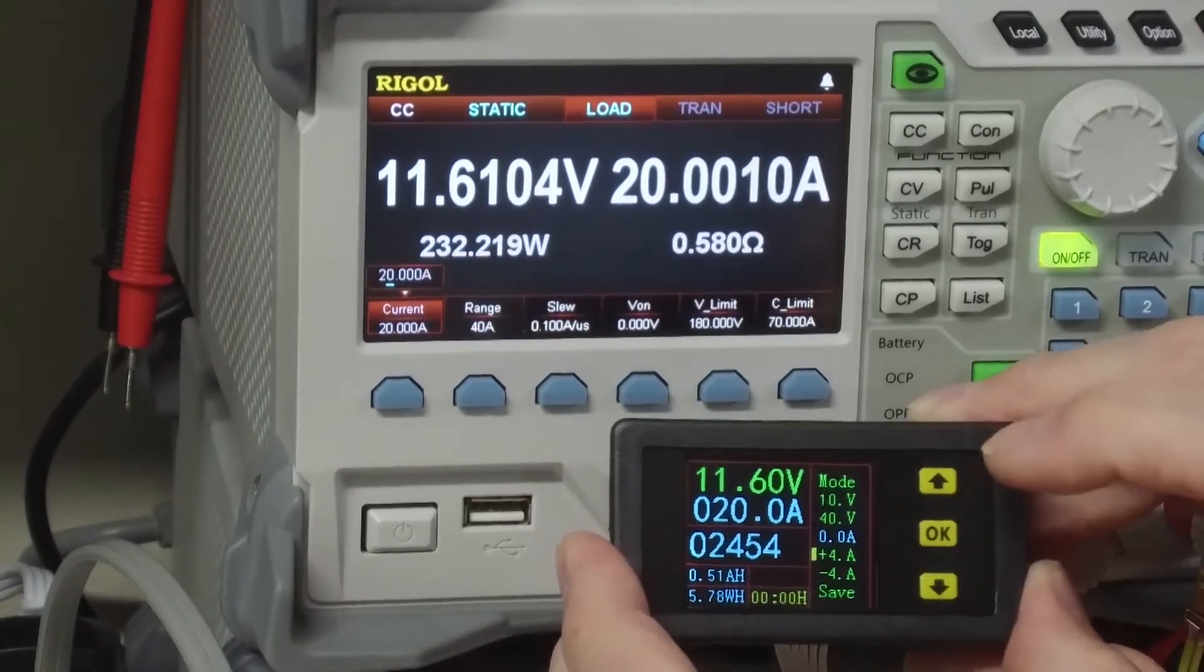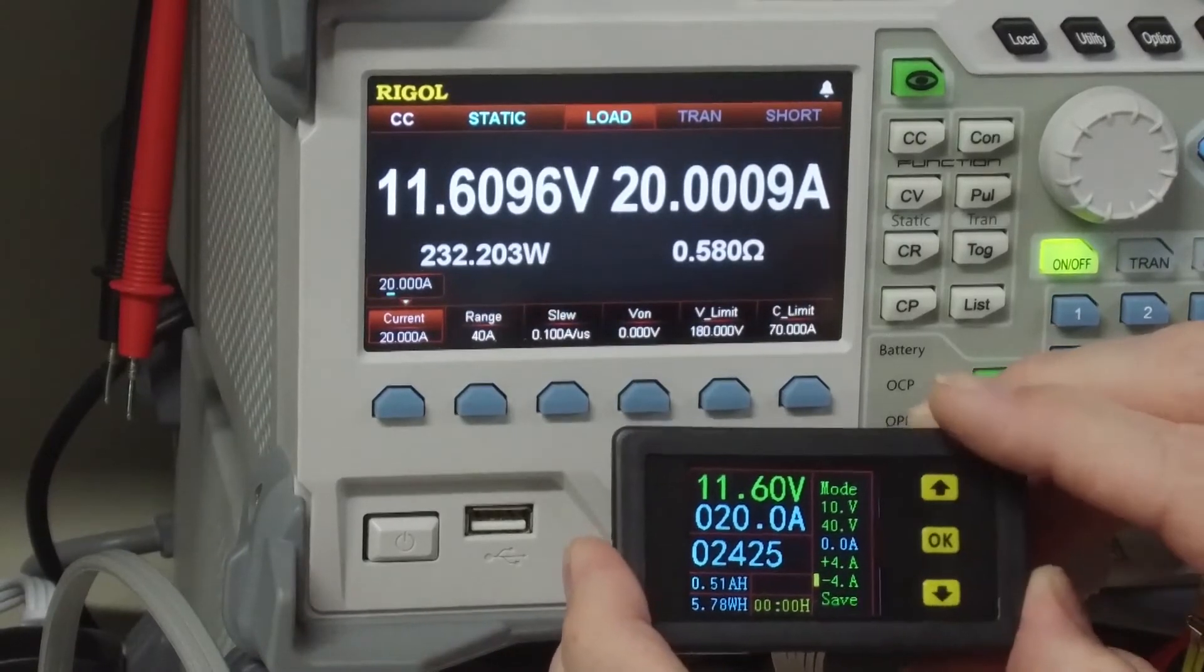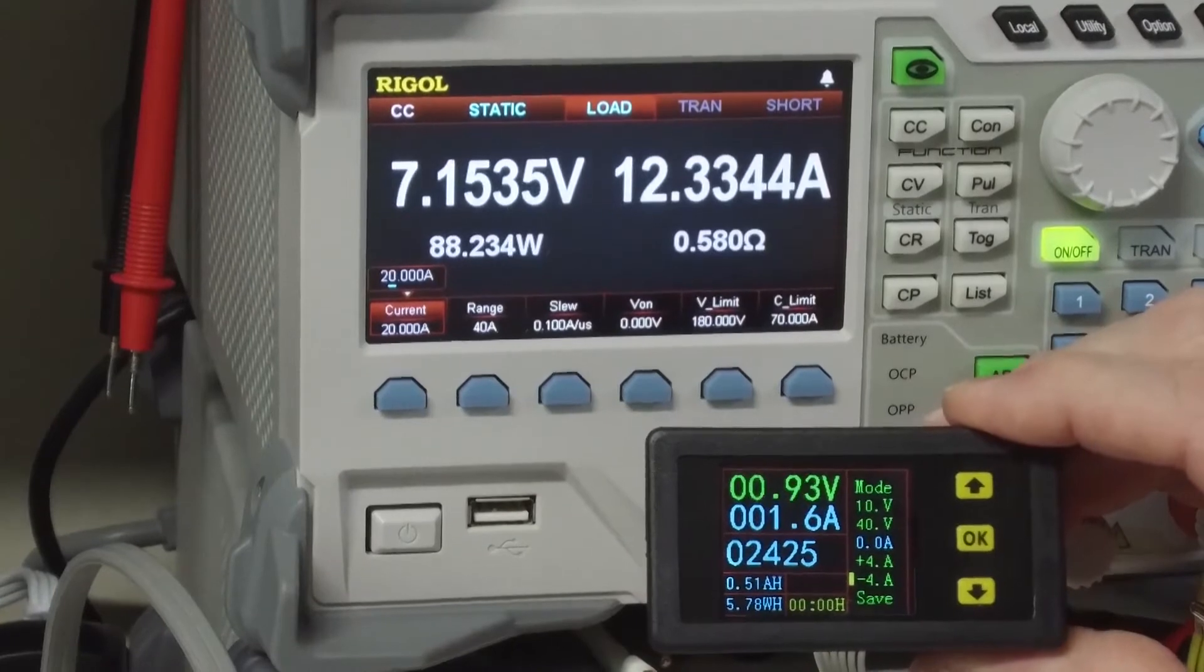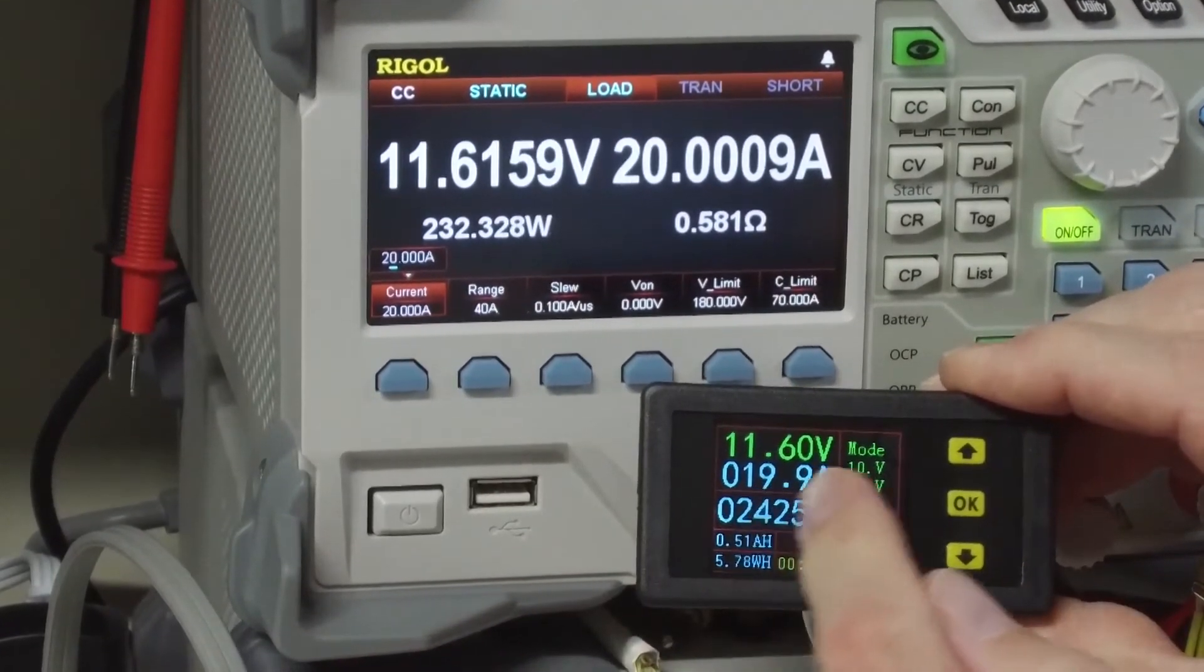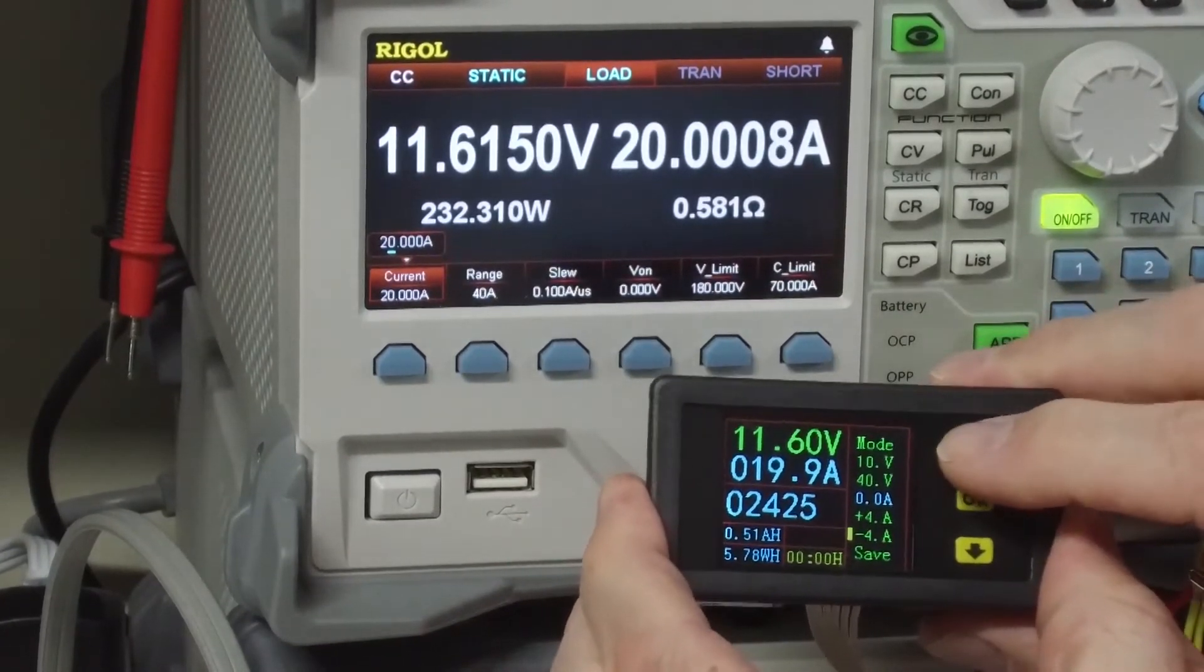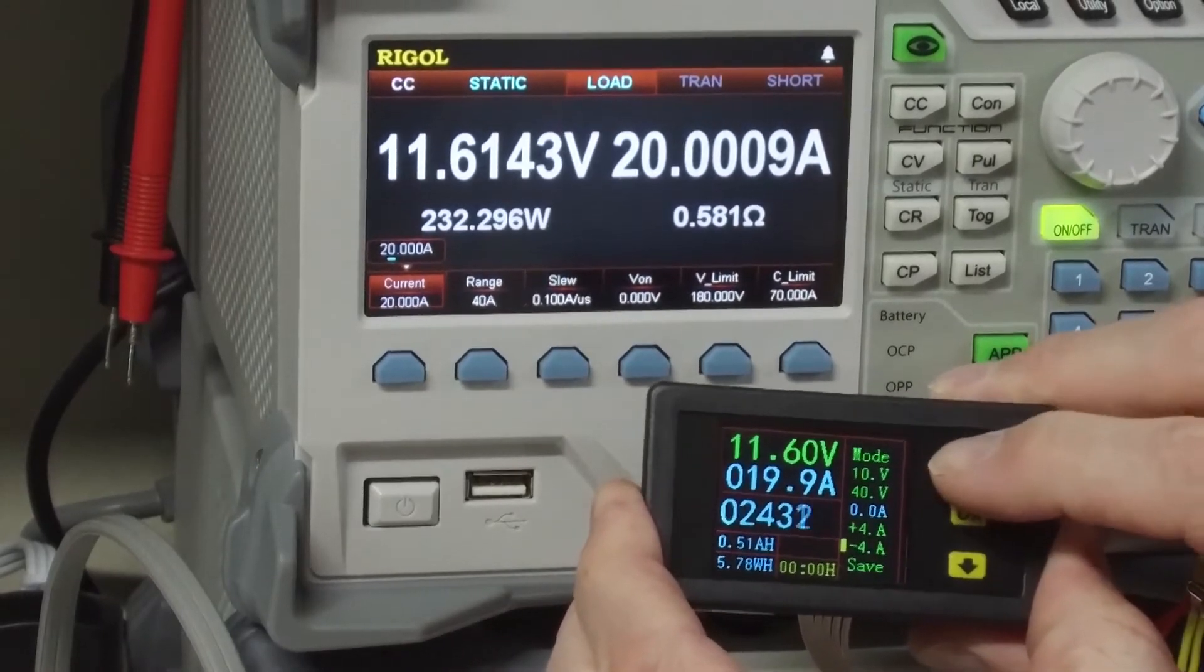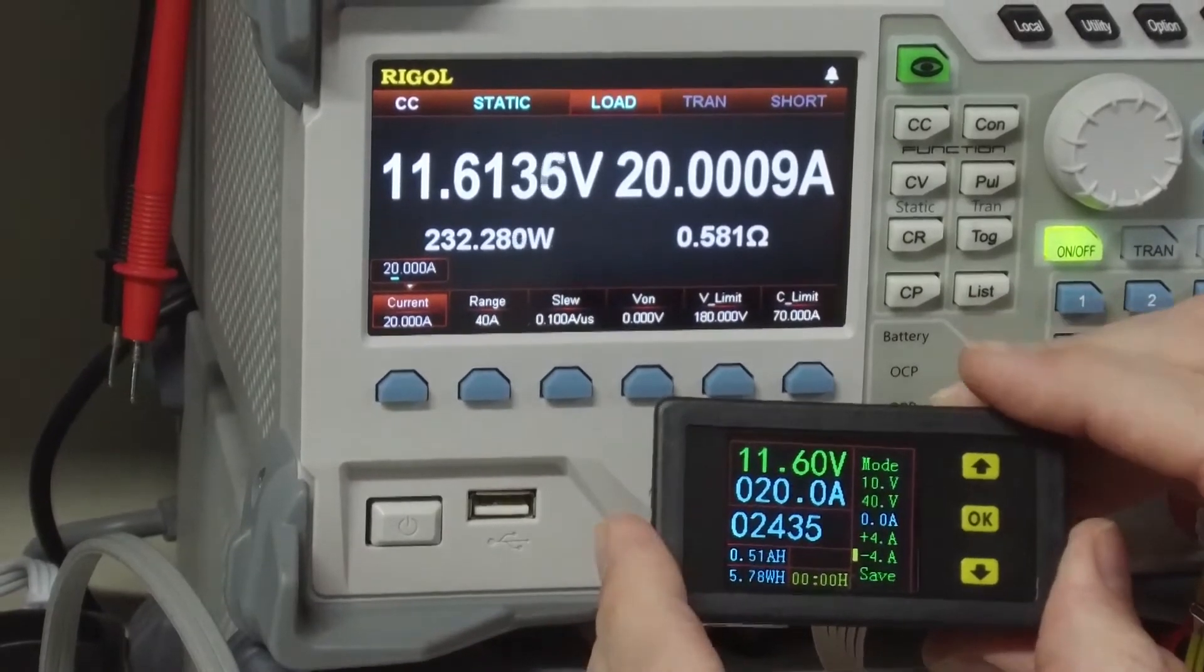Now what you want to do is you want to do another calibration with the current flowing the other direction. So I am going to flip my switch. And we can see that we are off just a little bit here. So I am going to adjust that. Now we are around 20 amps.